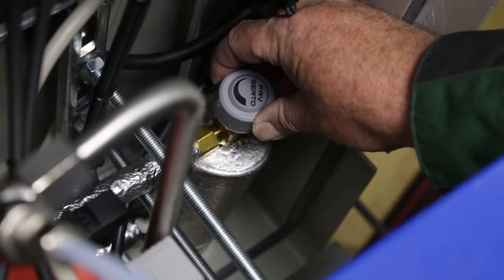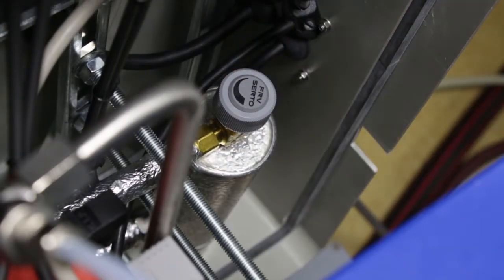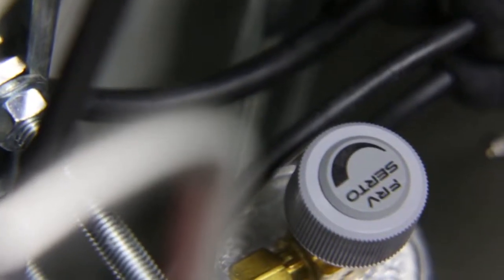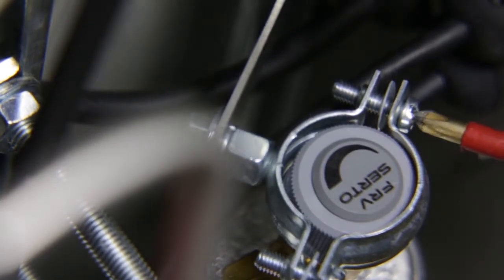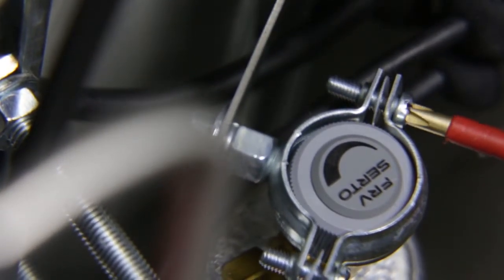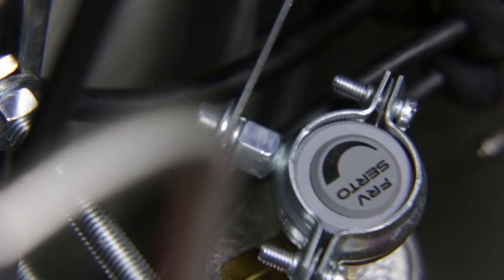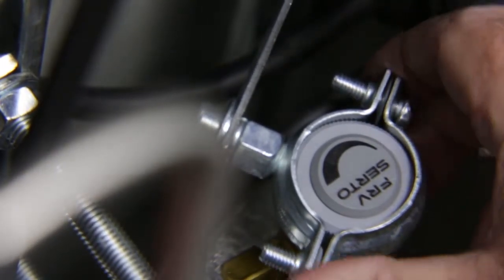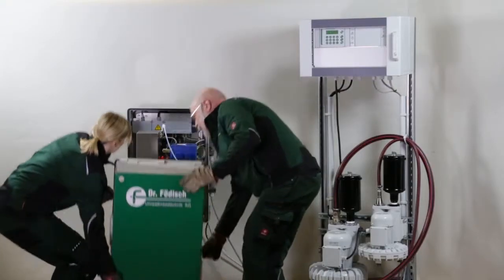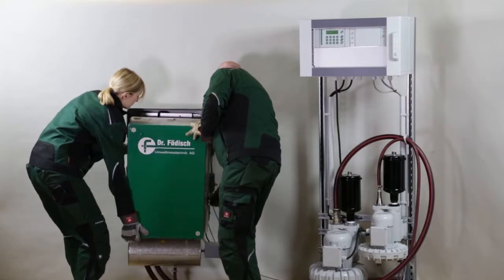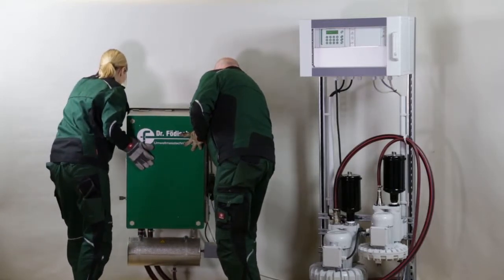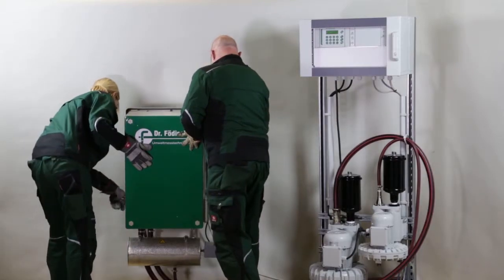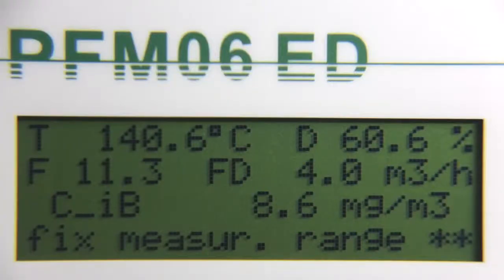Adjust the flow for the desired dilution of the measuring gas between 30% and 70% at the dilution air valve in the probe unit. Lock the valve for the dilution air against accidental readjusting. Put the cover on the enclosure and fix it. The PFM 06ED is in normal measuring mode.